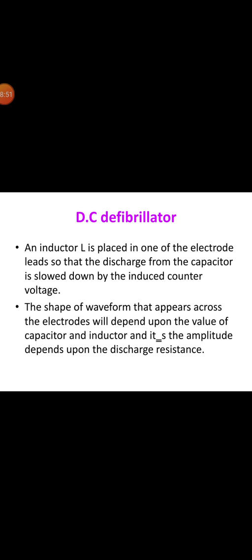Next, let us discuss the dual peak DC defibrillator. The passage of high current may damage the myocardium and the chest wall. To reduce the risk, some defibrillators produce a dual peak waveform. This keeps the stimulus at peak for a longer duration, and effective defibrillation at a desirable lower voltage level is possible with a truncated waveform also. This diagram shows the circuit of the dual peak DC defibrillator. Some energy can be applied to the heart at a low current level. Such defibrillators are called dual peak defibrillators, delay line defibrillators, or capacitor discharge DC defibrillators.